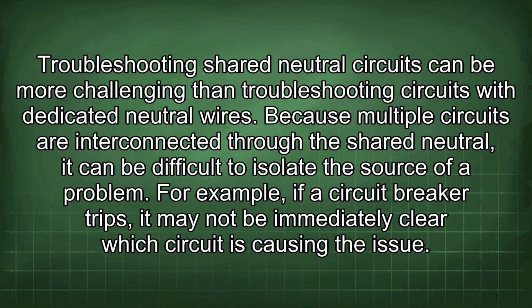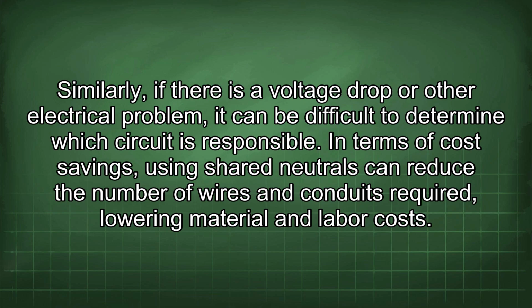Troubleshooting shared neutral circuits can be more challenging than troubleshooting circuits with dedicated neutral wires. Because multiple circuits are interconnected through the shared neutral, it can be difficult to isolate the source of a problem. For example, if a circuit breaker trips, it may not be immediately clear which circuit is causing the issue. Similarly, if there is a voltage drop or other electrical problem, it can be difficult to determine which circuit is responsible.